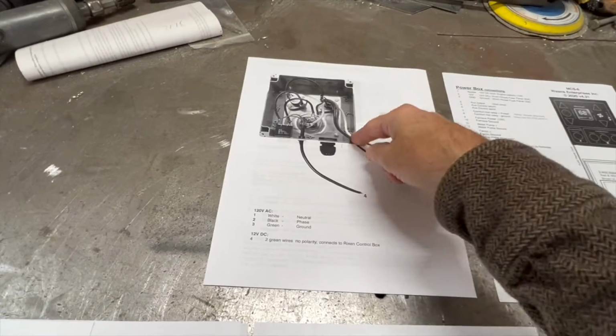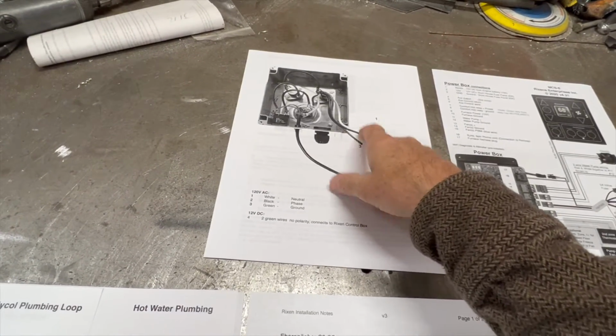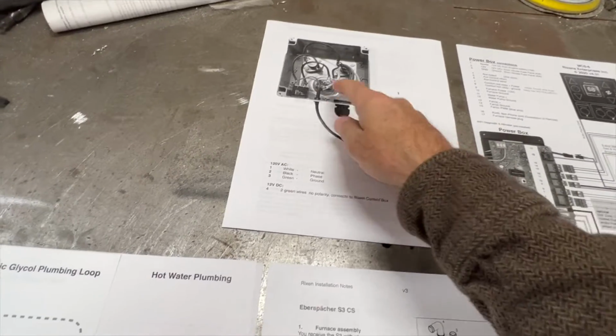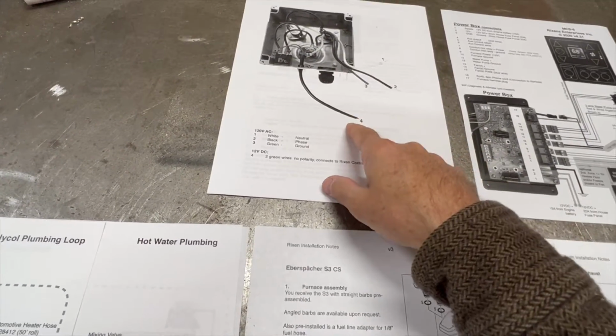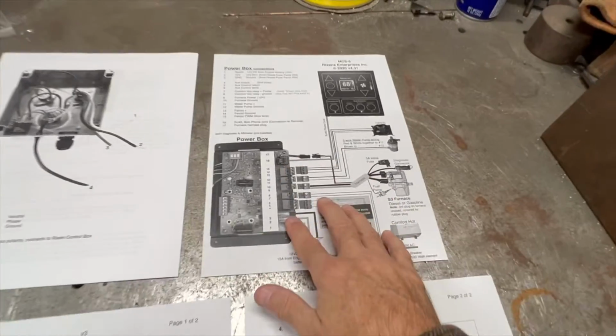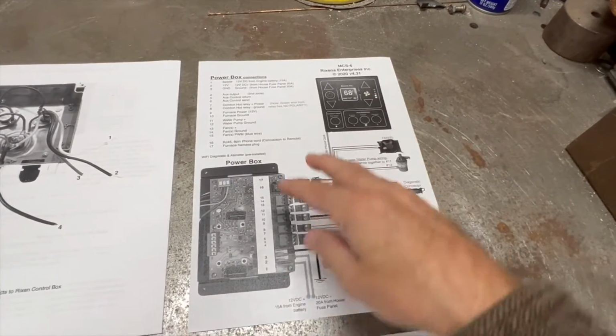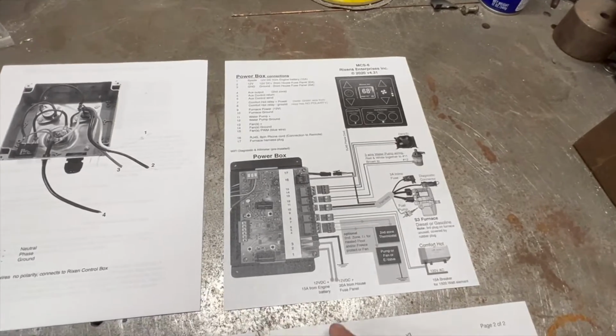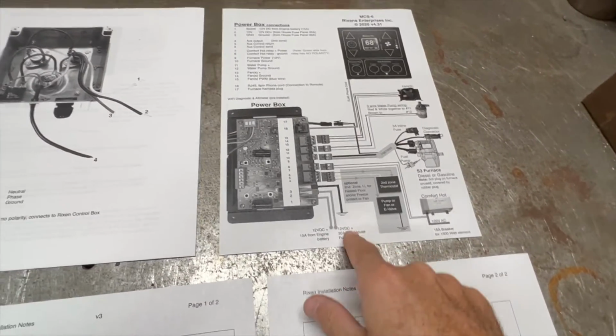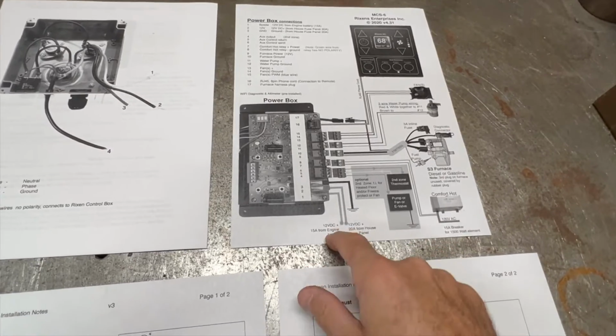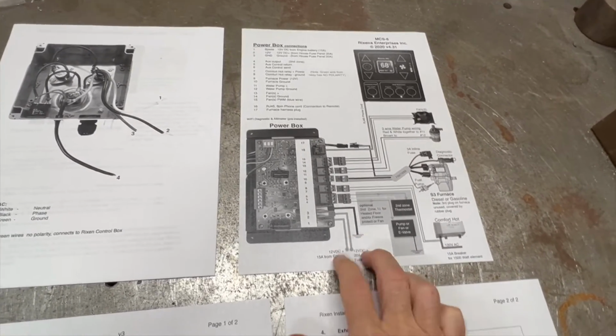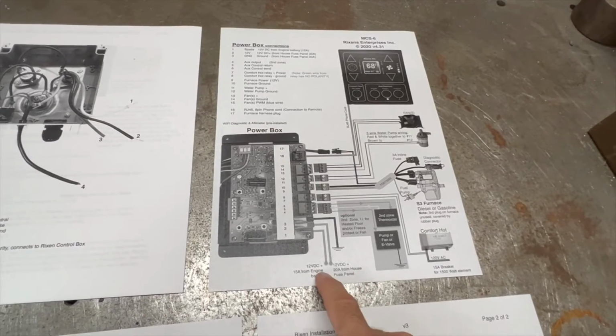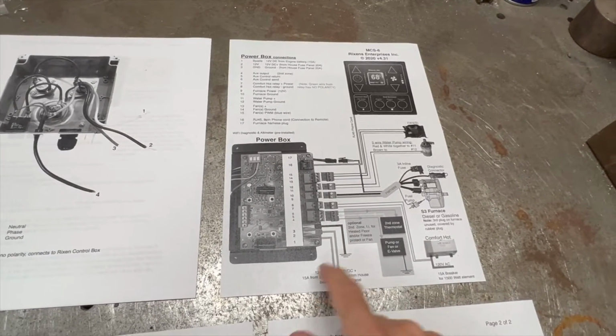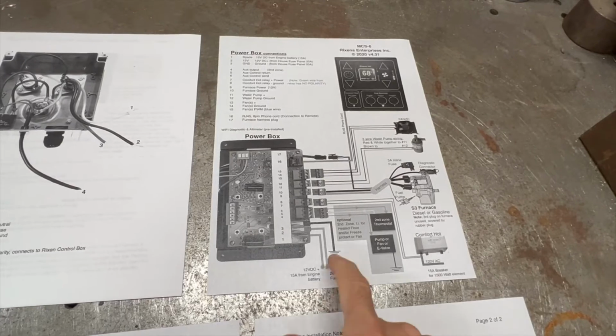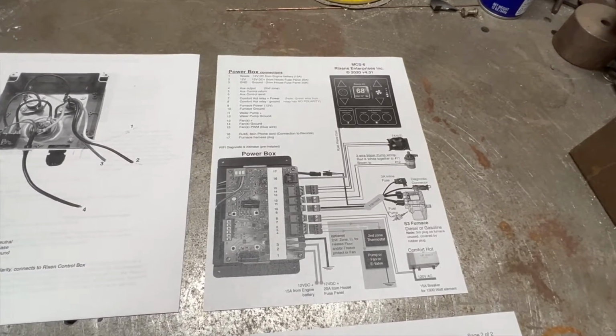This one cannot. Wiring for the 120 volt circuit is there for the heater inside the Comfort Hot, and there's a 12 volt connection also. The wiring instructions are laid out pretty well, showing you exactly what you need to wire. The only thing I found was there were actually two 12 volt DC connections, one with 20 amp and one with 15 amp. I didn't expect having two positive positions there, so I'm going to have to wire one more to come down to there.